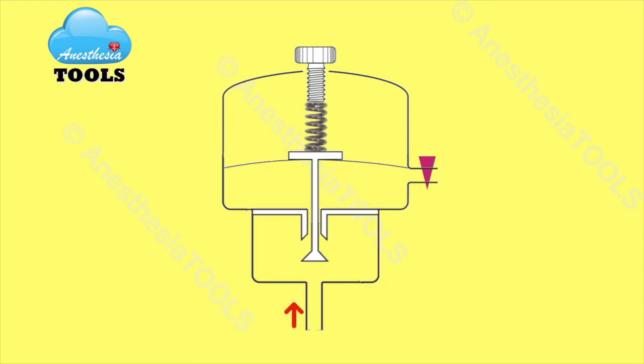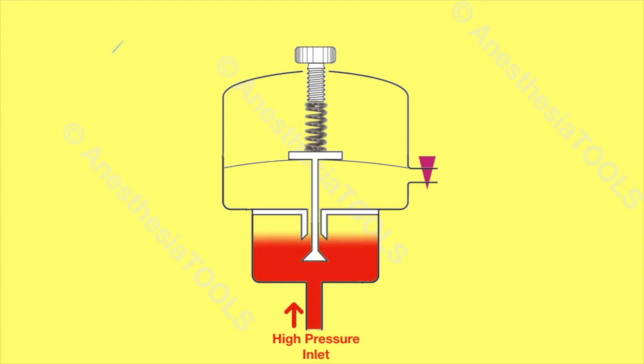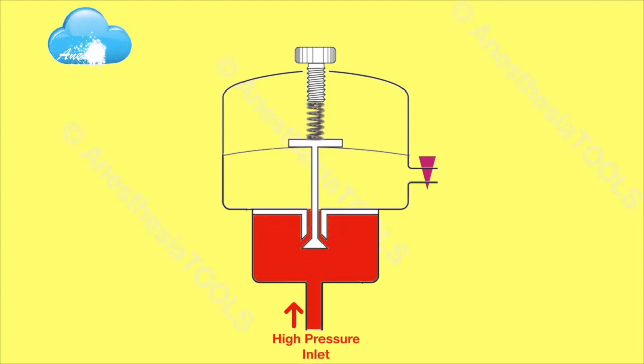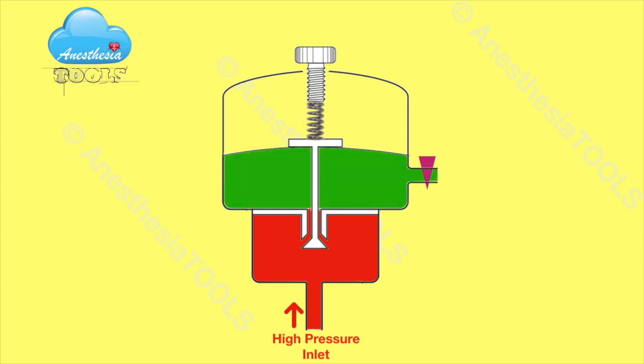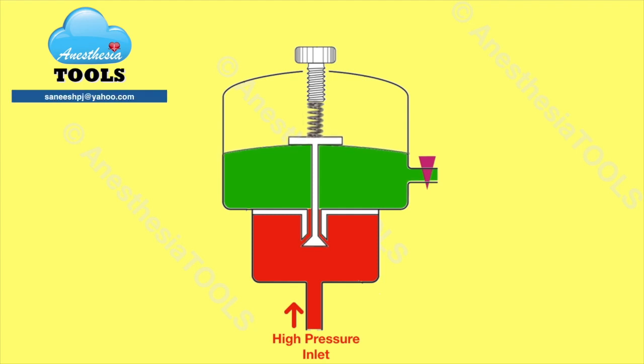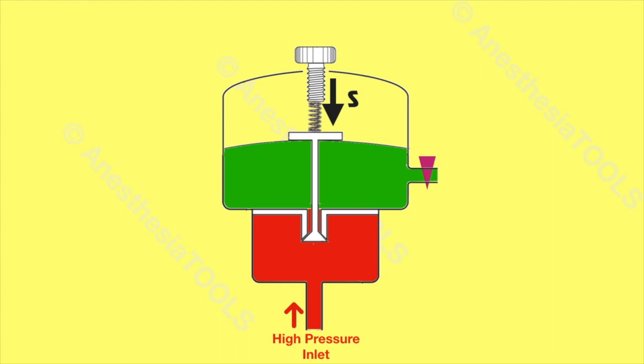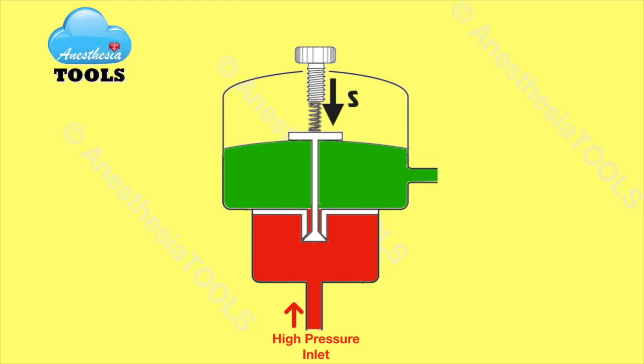Here, the gas from the cylinder flows into the inlet. In this diagram the outlet is closed. The gas flows across the valve into the low pressure chamber. As the diaphragm is pushed by the gas in the low pressure chamber, the valve seat moves up, closing the valve. Once the flow meter is open and the gas flows out from the low pressure outlet, the whole system assumes a new equilibrium.